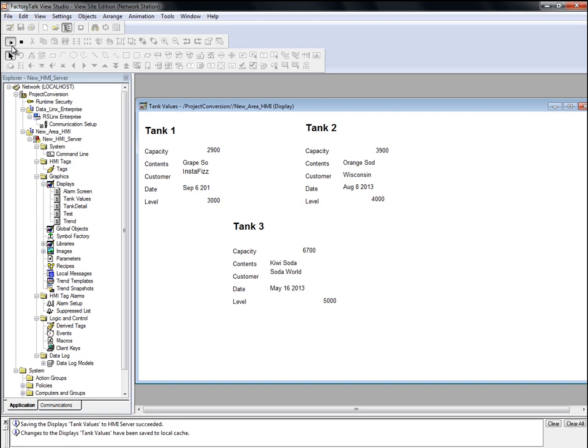So that's how you would use the Tag Converter Wizard utility to update your HMI device tag references to direct references. One thing to note when using the Tag Converter Wizard is that while all HMI device tags on a display are converted to direct references, any HMI memory tag references will remain unchanged.